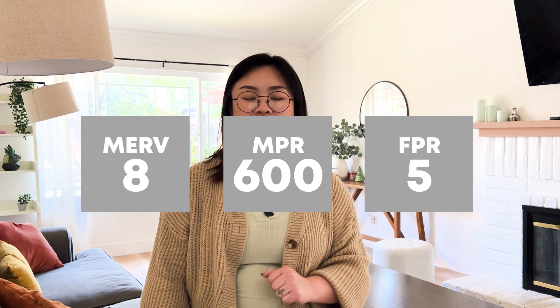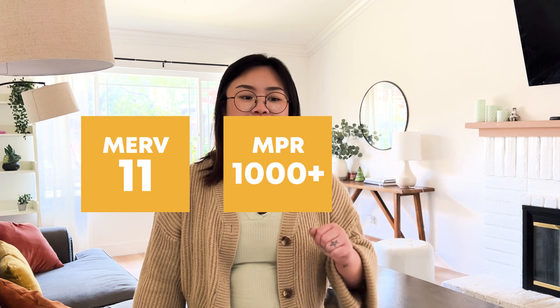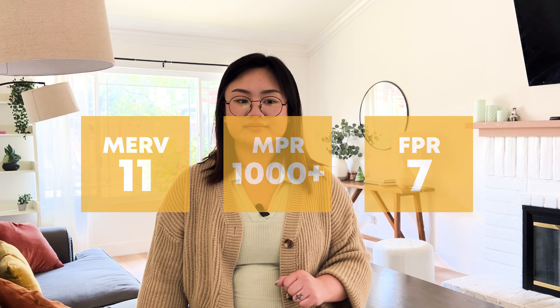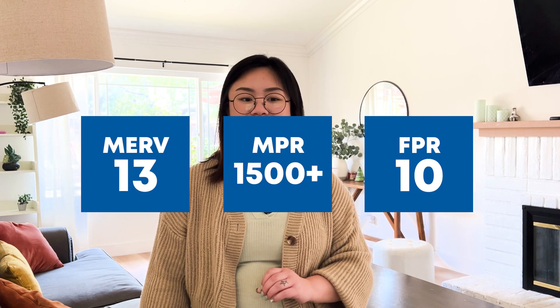Most HVAC techs will recommend at least a MERV 8. So to recap: if you're looking for basic filtration of lint, dust, pollen, and mold spores, choose MERV 8, MPR 600, or FPR 5. If you're looking for filtration of pet dander, smoke, and smog, choose MERV 11, MPR 1000 through 1200, and FPR 7. If you're looking for filtration of bacteria and viruses, or you have extreme allergies, choose MERV 13, MPR 1500 through 1900, or FPR 10.